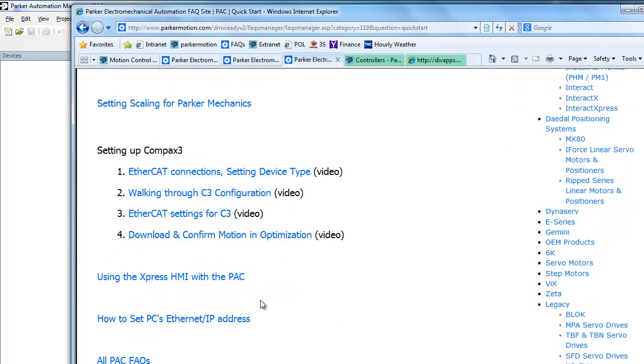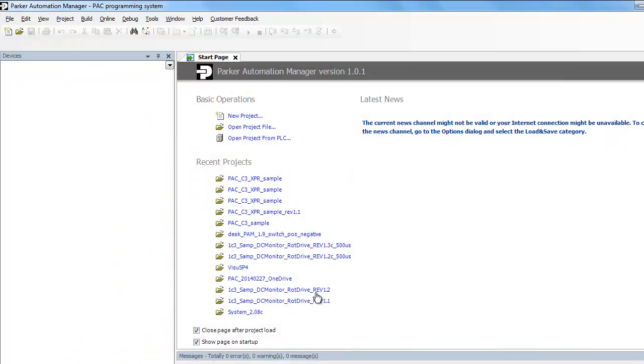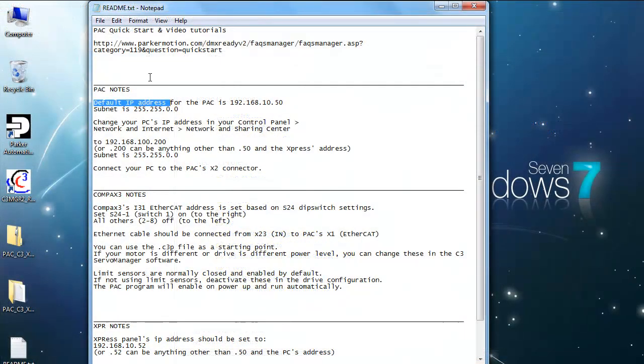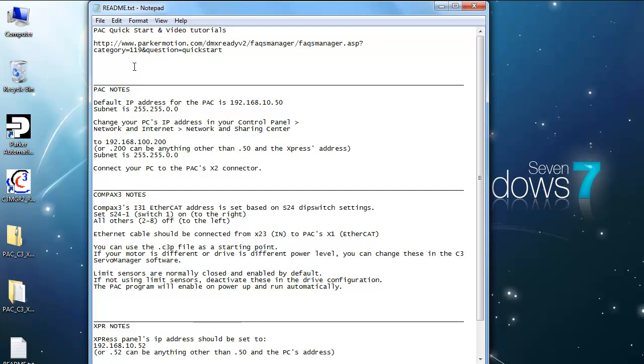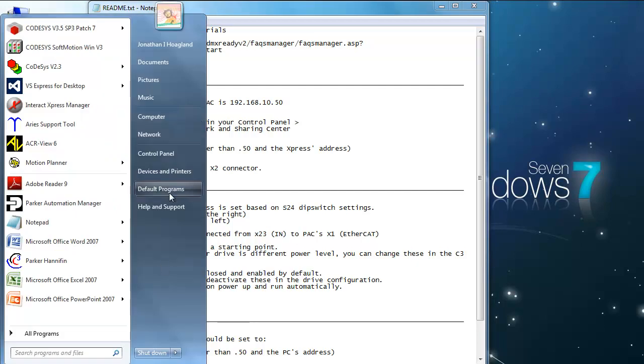There's also additional information on the Express HMI settings for the PAC controller, and a video showing how to set the PC's Ethernet address. You'll notice under the PAC notes that the default address for the PAC controller is 192.168.10.50, and the subnet is 255.255.0.0.